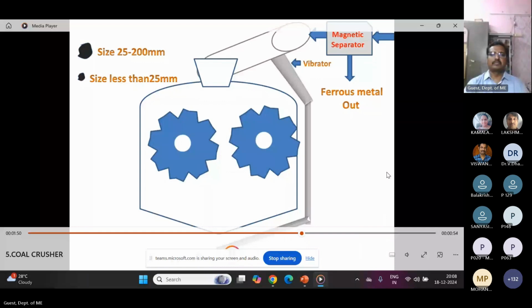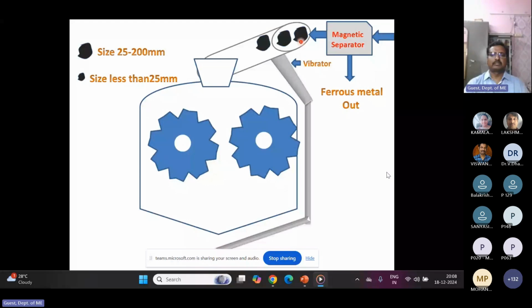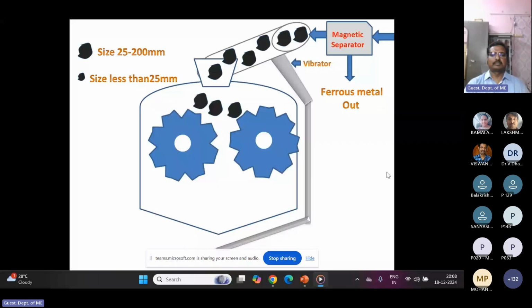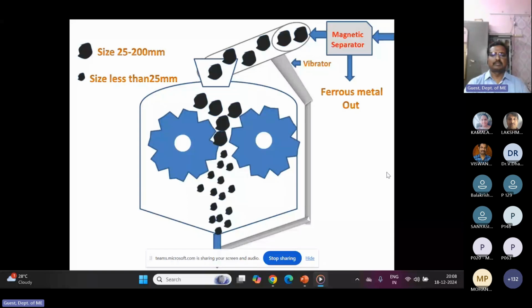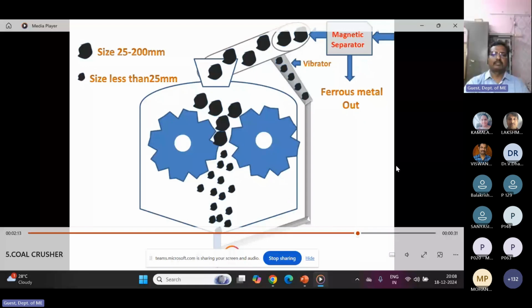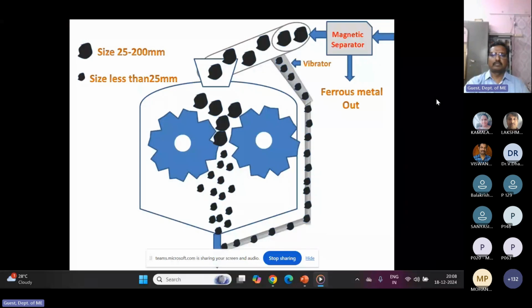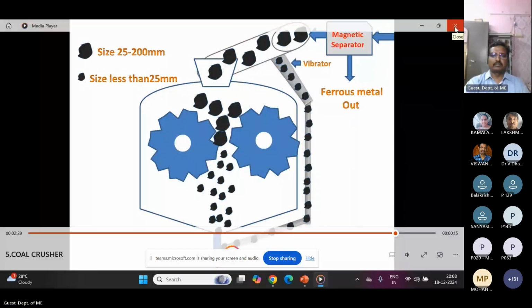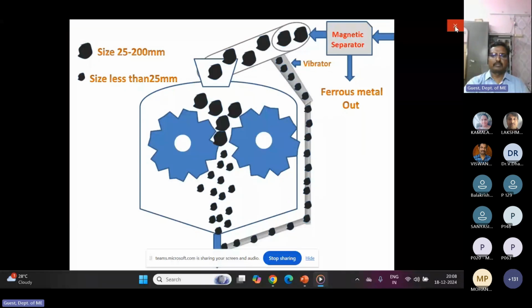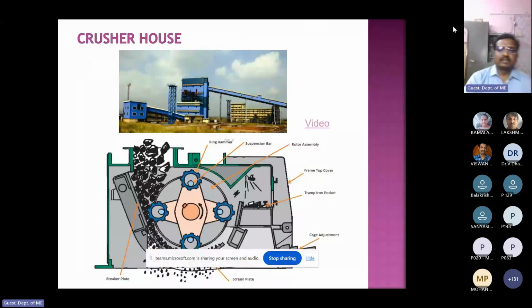Now what will happen? Coal will come after the magnetic separator, and then the crusher will rotate and crush the coal, and our crushed coal will go directly to the chamber where we want to move it, or directly to the power plant. The vibrator also separates the small coal pieces, which go and meet this coal and go to the chamber where we want to send the coal. So this is the working of a coal crusher for crushing coal into small pieces, so that we can use the coal easily. Okay, after crushing the coal to 20 mm size, it is sent to the bunkers.